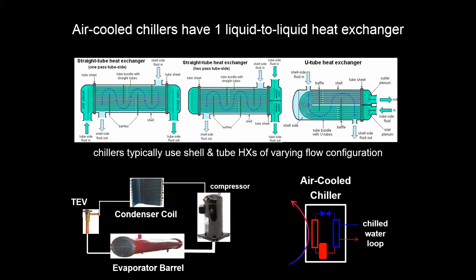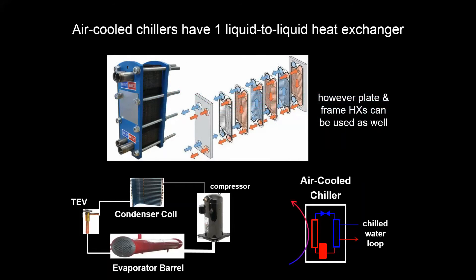So regardless of the type of chiller, it's always going to have an evaporator barrel. That can come in a couple different configurations depending on how the refrigerant is indirectly interacting with the chill water going past it or alongside it. There could also be a plate and frame heat exchanger, although this is more rare.